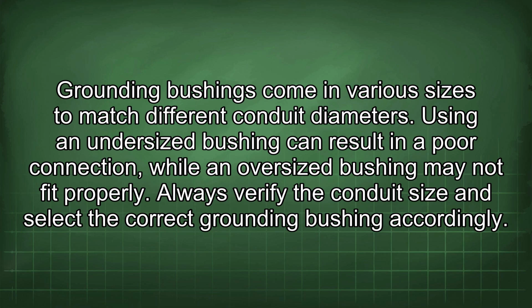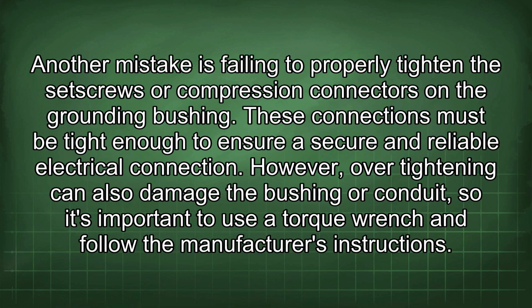Using an undersized bushing can result in a poor connection, while an oversized bushing may not fit properly. Always verify the conduit size and select the correct grounding bushing accordingly. Another mistake is failing to properly tighten the set screws or compression connectors in the grounding bushing. These connections must be tight enough to ensure a secure and reliable electrical connection.